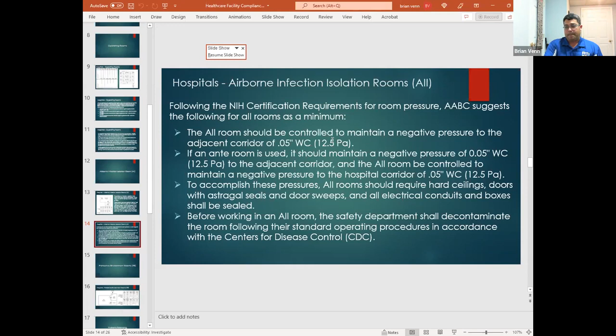And again, all electrical conduits need to be sealed, because I've run into problems where we really took a room to task on why it wasn't passing and leaking. When we traced the electrical conduit all the way back to the mechanical room, you could feel nice, cool, conditioned air coming out of that conduit, which served the OR rooms. Once we put those seals in place, suddenly the room passed, and it was really just the electrical conduits at that point that were costing us the room performance.